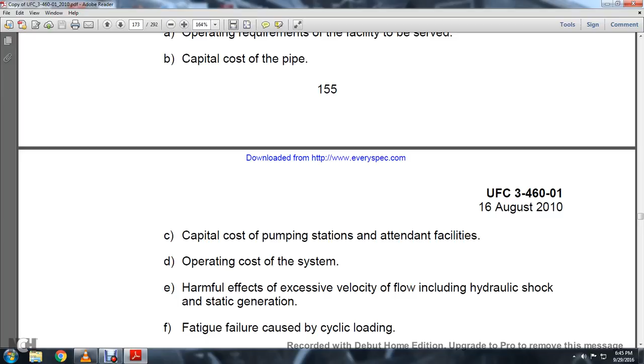9.2.2 Piping arrangement. When possible, arrange the pipe in parallel groups to facilitate multiple use of the supports, to minimize the amount of trenching for underground piping, and to minimize the number of steps and stiles needed across the pipe runs for underground and aboveground applications. Consider constructability when determining the amount of space between the pipes, using the following criteria.